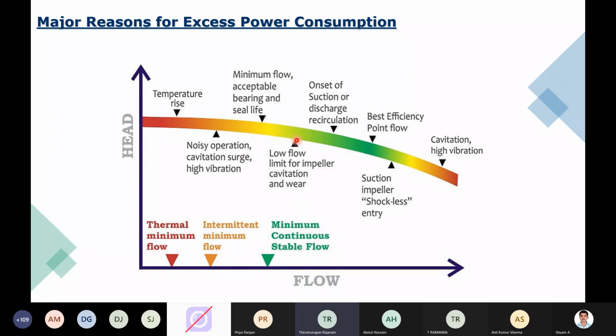So this is your low flow limit, in which you also need to have a sufficient amount of flow getting into the product to avoid cavitation and wear and tear. And yeah, so we have this minimum continuous stable flow, intermittent minimum flow situations, and thermal minimum flow. So the diagram itself tells you what would be your ideal zone to operate. And you have suction impeller shockless entry situation, and cavitation and high vibration.